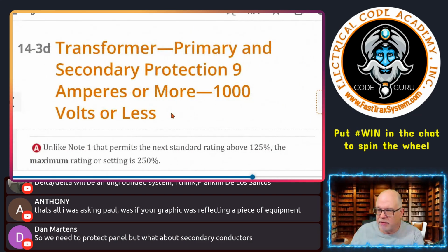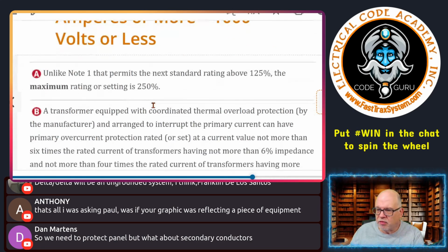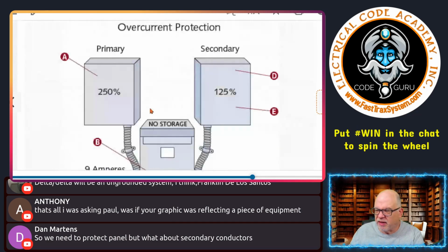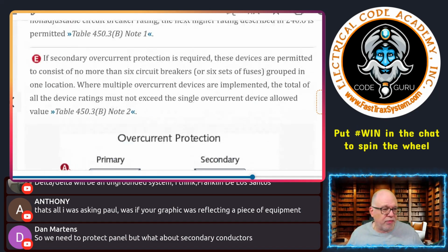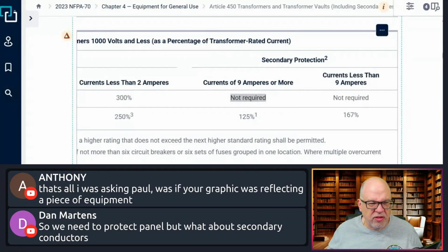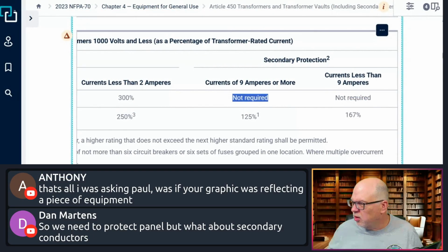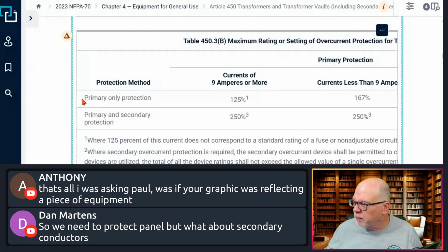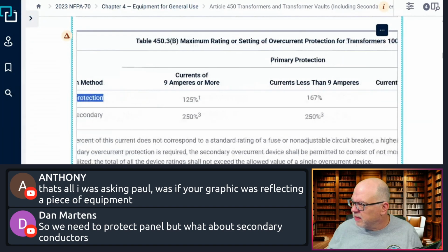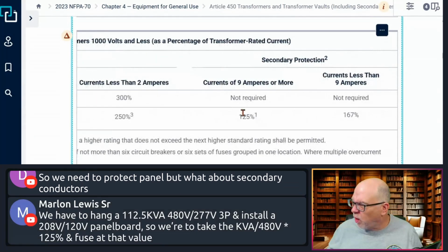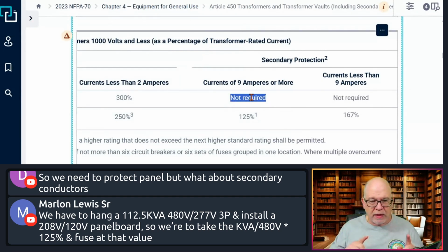Let's see here. I was hoping we'd show a graphic. Okay, so that was the primary protection right here. So this is simply a situation where I have primary only protection and I do not require secondary protection for that transformer. Okay, so I'm not required to have the secondary protection in this scenario. And we're only talking about protecting the transformer.